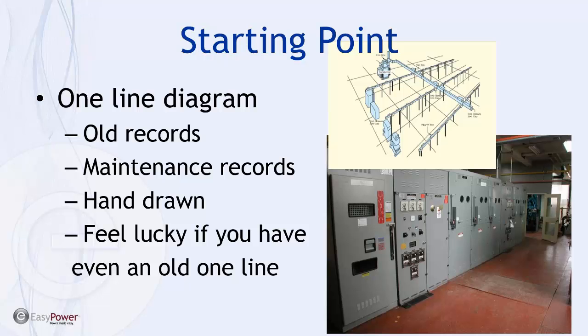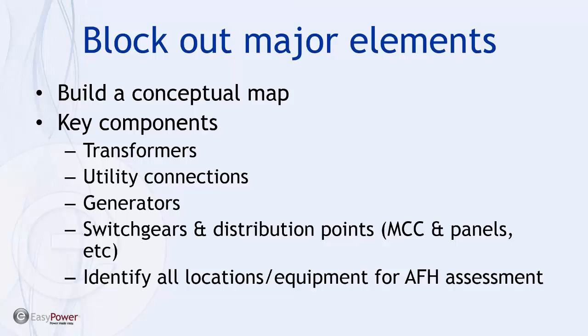A lot may be based upon tribal knowledge of the maintenance team and what people understand the layout to be. What I would suggest is to start with a hand-drawn version of what the one-line diagram looks like, or at least what you think it looks like. If you're lucky and have even an old one-line diagram, that's an excellent place to start. The name of the game is getting started, and once you understand what's missing, you need to build a conceptual map of how to address this overall project of doing data collection.